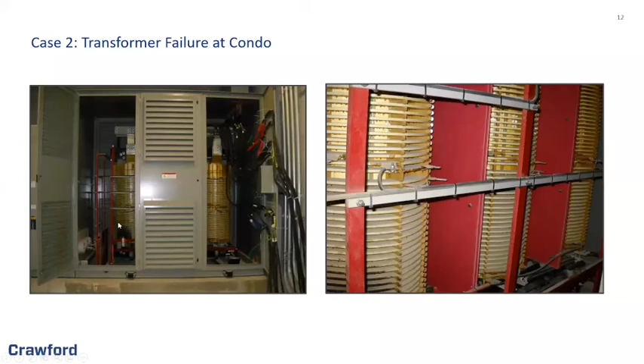The engineer had also determined that a temporary repair could be completed on this transformer, so power could be restored to the building while we awaited a new transformer to be manufactured, and thus we would be eliminating the extensive rental generator and fuel costs. So here are some photos. You see some damages down there to, I believe that's the high voltage coil on this transformer.